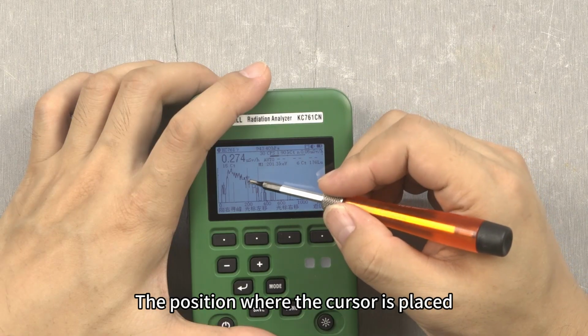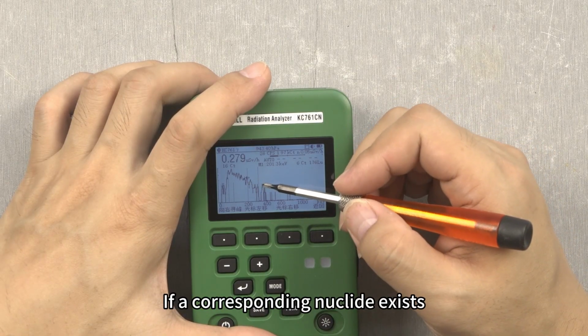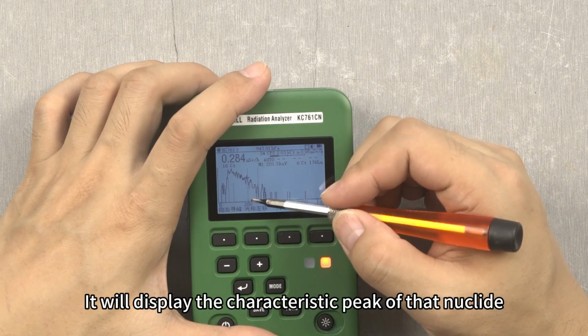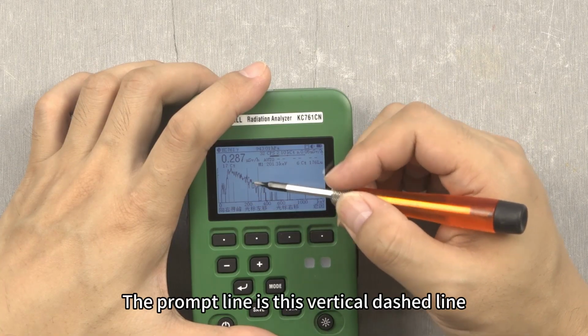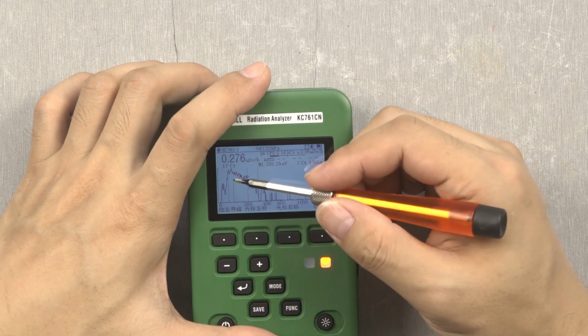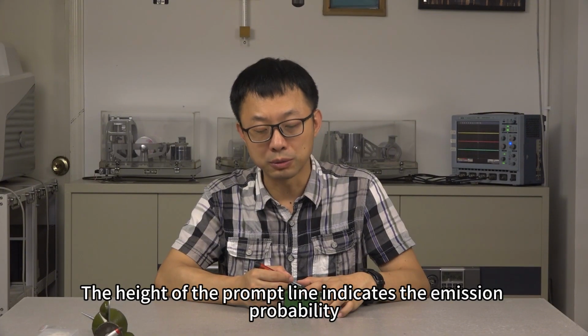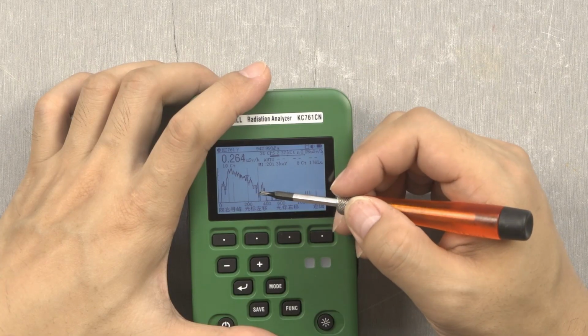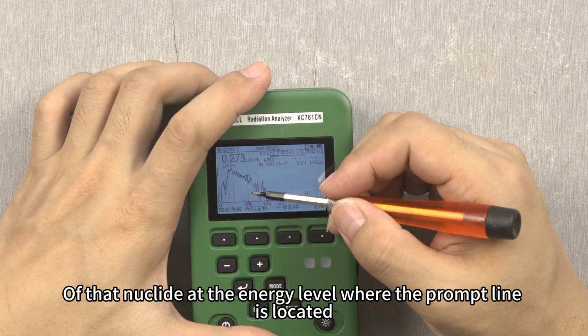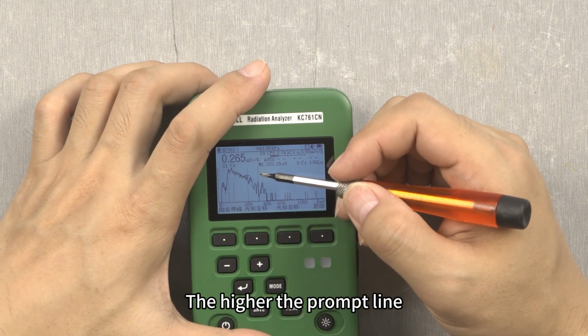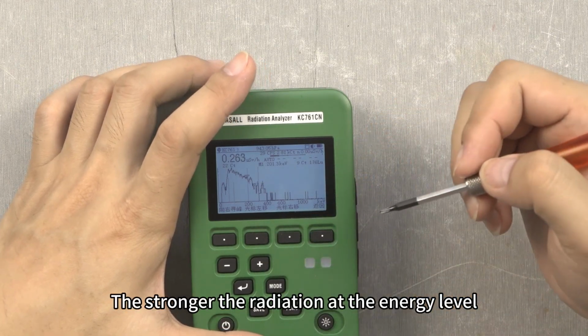If a corresponding nuclide exists at the cursor position, it will display the characteristic peak of that nuclide. The prompt line is this vertical dashed line. The height of the prompt line indicates the emission probability of that nuclide at that energy level. The higher the prompt line, the stronger the radiation at that energy level.